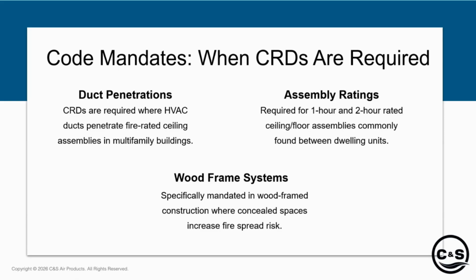So, when CRDs are required: duct penetrations, any kind of opening that you see, and then the wood frame systems, that's really where you're going to see a lot of ceiling radiation dampers. In non-combustible construction, you'll see a lot more fire dampers and fire smoke dampers as they go through the walls or the fire rated floors. But with wood construction, you'll definitely see them going through the actual ceiling space and the hard deck to run their ductwork and make sure that the air is supplied through the units.